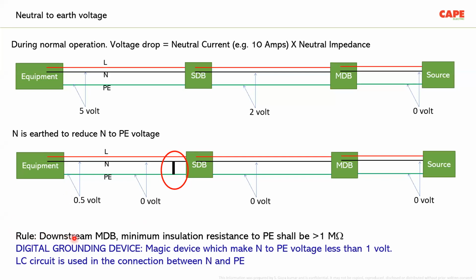The rule says downstream of the main distribution board, the minimum insulation resistance to PE shall be greater than or equal to 1 megohm. So here, where I'm moving the cursor, you have the main distribution board. From there, downstream up to the equipment, the minimum insulation resistance is 1 megohm. If you make a connection, if you earth the neutral downstream, then this rule is violated.